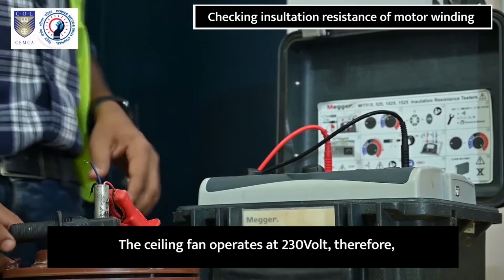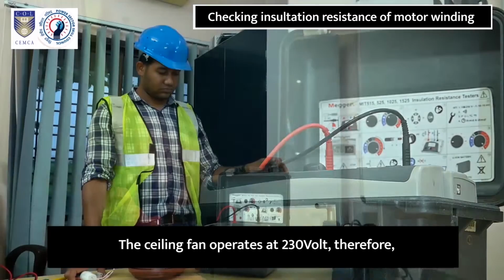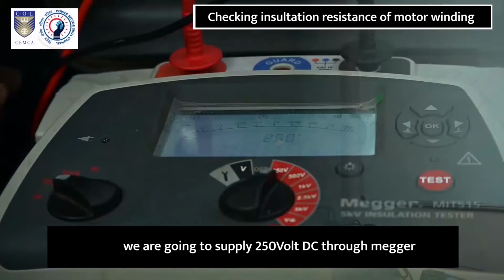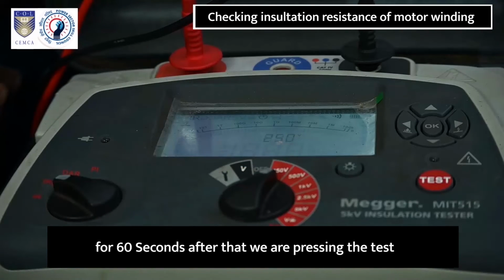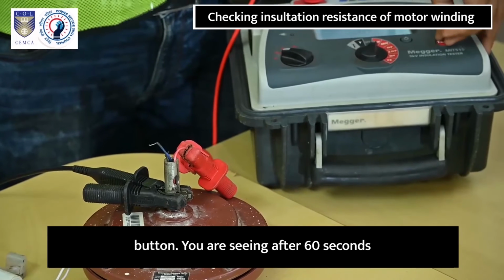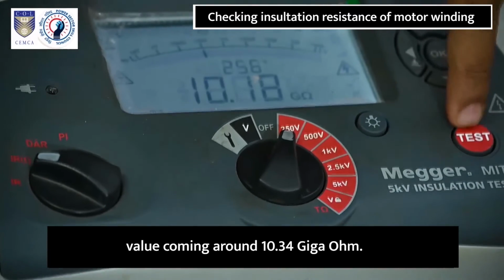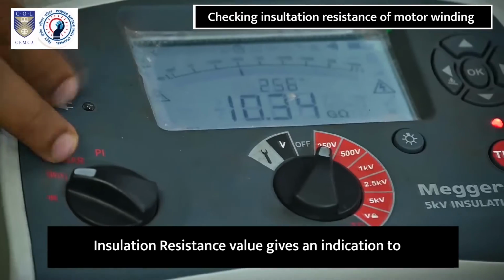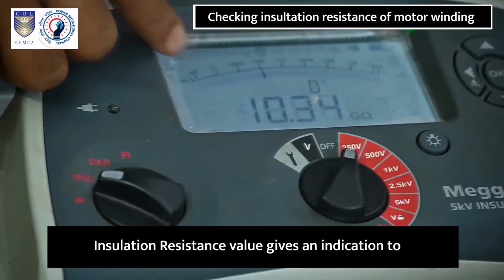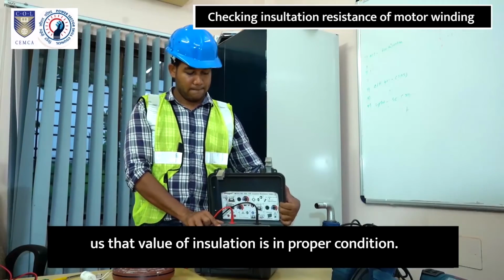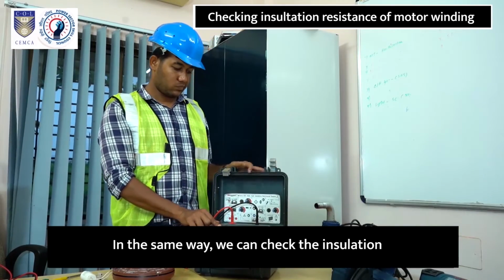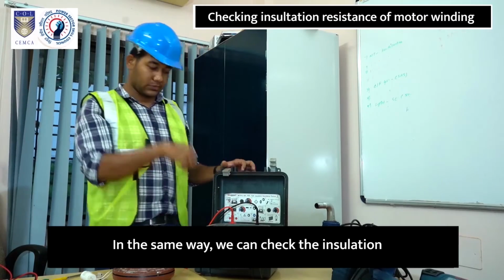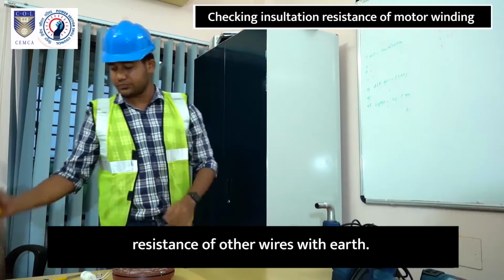The ceiling fan operates at 230 volt. Therefore, we are going to supply 250 volt DC through the megger for 60 seconds. After that, we are pressing the test button. You're seeing after 60 seconds the value is coming around 10.34 gigaohm. The insulation resistance value gives us an indication that the insulation is in proper condition. In the same way, we can check the insulation resistance of other wires with earth.